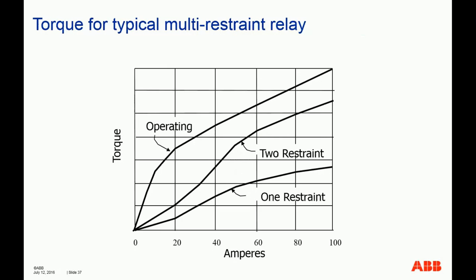the relay manufacturer will issue a plot, a graph, a design. That's how they design their relay. It's all about torque. If your operating torque is higher than your restraint torque, the relay operates. If your restraint torque is higher than the operating torque, the relay restrains. So that's why, as you can see here, for the 60 amp restraint, for example, and depending on whether you have 1 restraint, 2 restraint or 3 restraint, you will require a different amount of operating torque in order to operate.